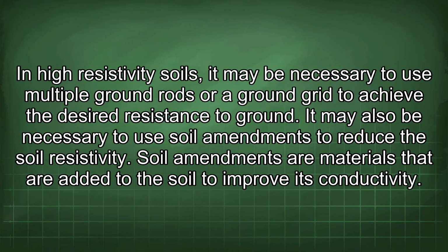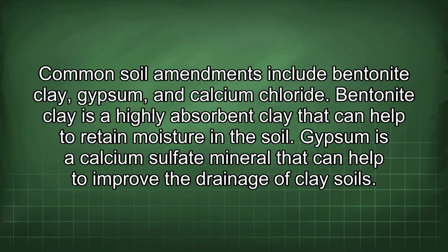In high resistivity soils, it may be necessary to use multiple ground rods or a ground grid to achieve the desired resistance to ground. It may also be necessary to use soil amendments to reduce the soil resistivity. Soil amendments are materials that are added to the soil to improve its conductivity. Common soil amendments include bentonite clay, gypsum, and calcium chloride.